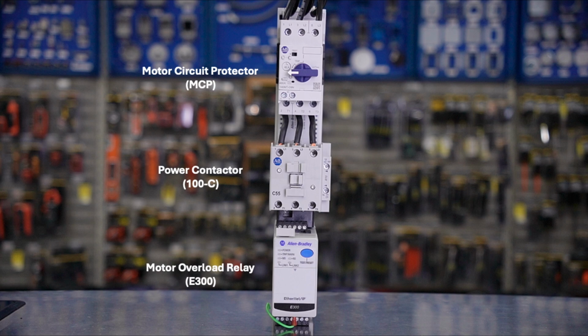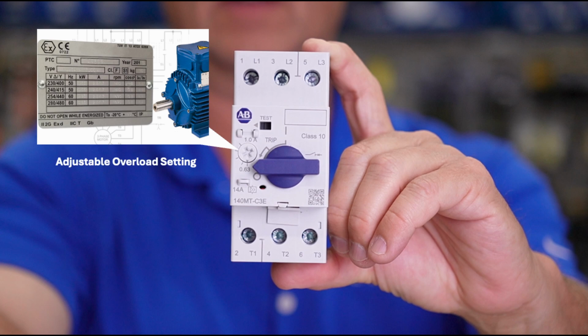And that leaves us with the granddaddy of them all, the motor protection circuit breaker, or MPCB. As its name implies, an MPCB combines the short circuit capabilities of a motor circuit protector with the motor thermal overload protection of an overload relay. The built-in adjustable overcurrent feature allows you to match the trip setting on the breaker to the full load amperage rating on your motor. The MPCB also protects motors against phase loss and undervoltage conditions.